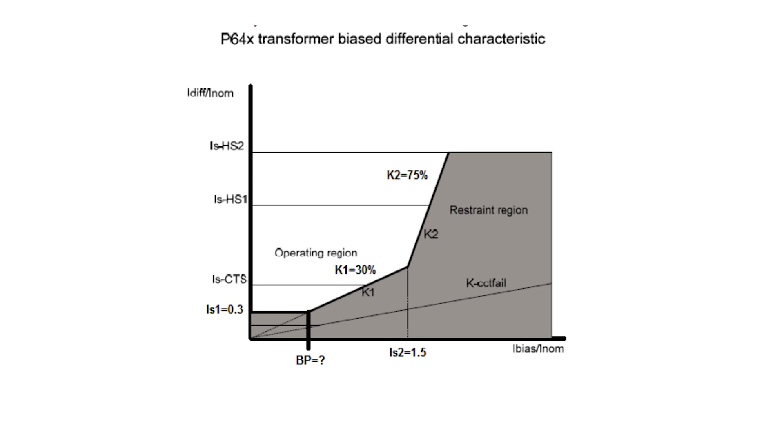To verify the slope characteristics, we need to divide this test case into three segments. The first segment is the zero slope minimum pickup characteristics. The second segment is the slope 1 characteristics. The third segment is the slope 2 characteristics.